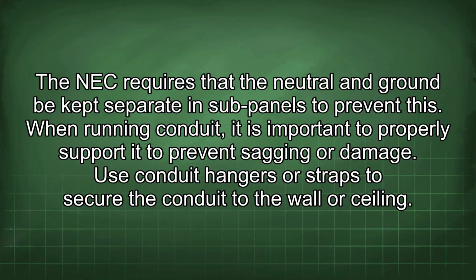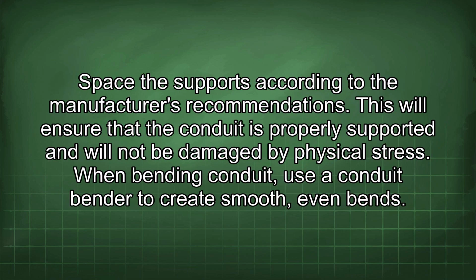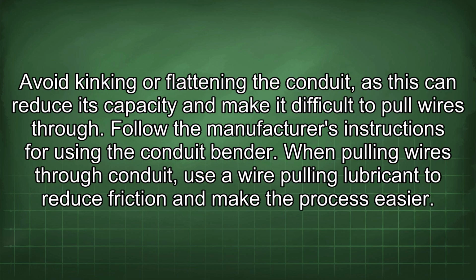When running conduit, it is important to properly support it to prevent sagging or damage. Use conduit hangers or straps to secure the conduit to the wall or ceiling. Space the supports according to the manufacturer's recommendations. This will ensure that the conduit is properly supported and will not be damaged by physical stress. When bending conduit, use a conduit bender to create smooth, even bends. Avoid kinking or flattening the conduit, as this can reduce its capacity and make it difficult to pull wires through. Follow the manufacturer's instructions for using the conduit bender.